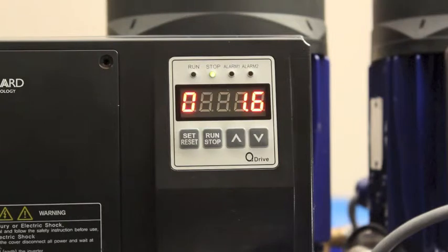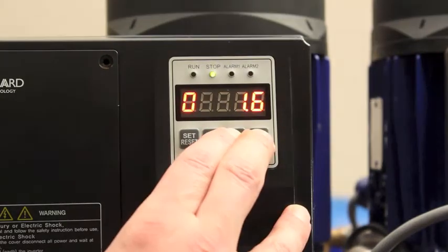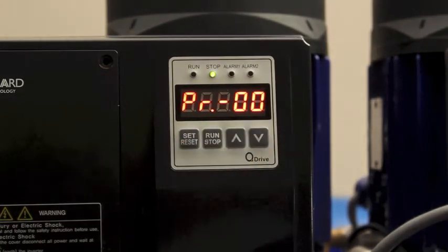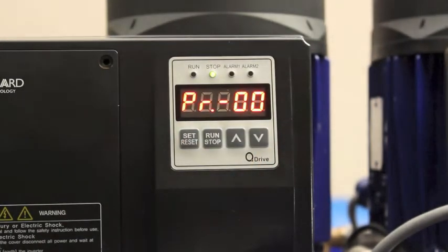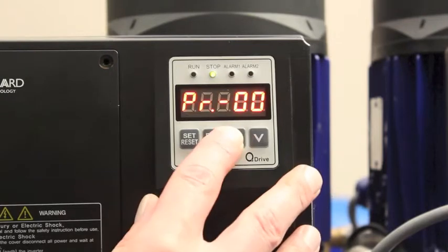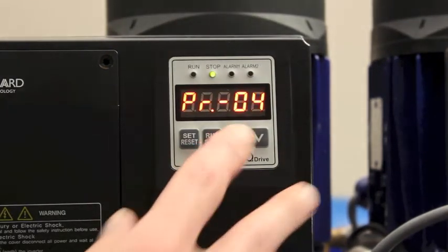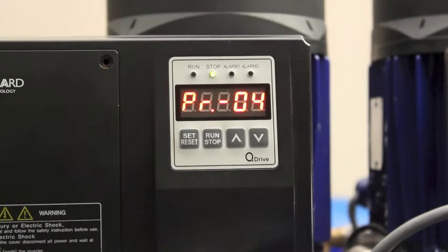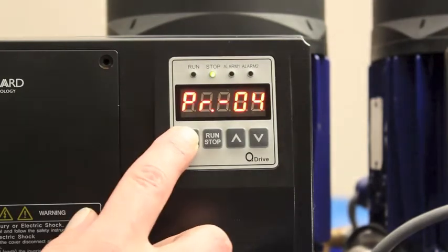When the pump is in stop, press the up and down buttons together for a couple of seconds to enter the PR menu. Use the up or down buttons to find PR4. This is the adjustment parameter for the discharge transducer, or PR6, which is the adjustment parameter for the inlet transducer. When the desired adjustment parameter is selected, press the Set Reset button for a couple of seconds.